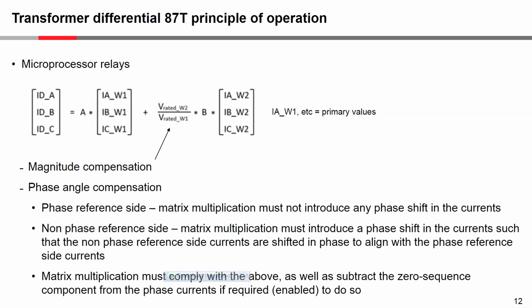And we saw that with the delta connection for the pre-microprocessor based relays, where the CT secondary delta connection was actually performing that phase rotation to align with the delta side of the transformer, which, with the direct Y-connected CTs, was the phase reference. So this must do exactly the same. And the matrix multiplication must comply with the above, as well as subtract the zero sequence component if required or if set to do so. Okay.